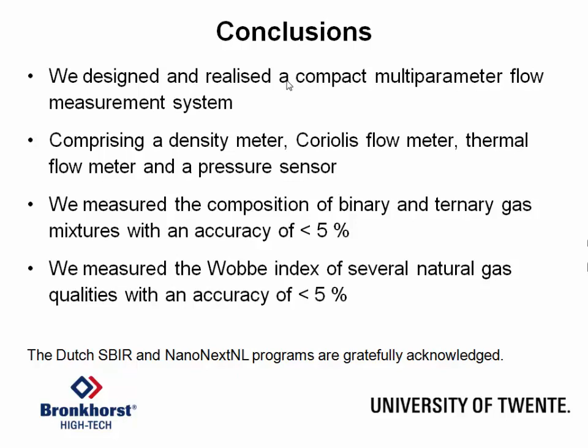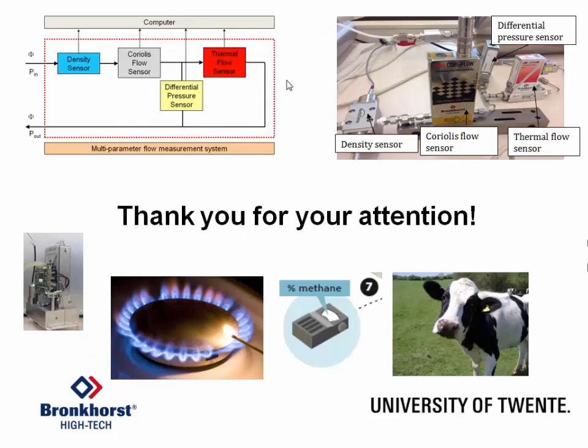So in conclusion, we designed and realized a compact multi-parameter flow measurement system which consisted of a density meter, Coriolis flow meter, thermal flow meter and a pressure sensor, all off the shelf. And we measured the composition of binary and ternary gas mixtures with an accuracy within 5%. And the same goes for the Wobbe index of 11 natural gas compositions, also within 5%. And in the future we will improve the system further. So thank you for your attention.